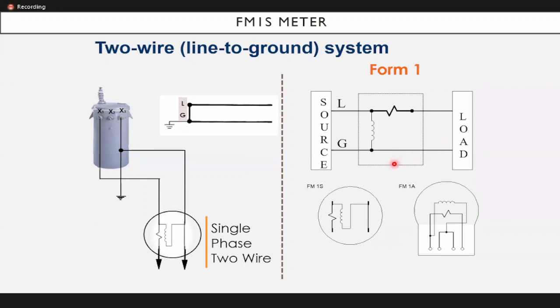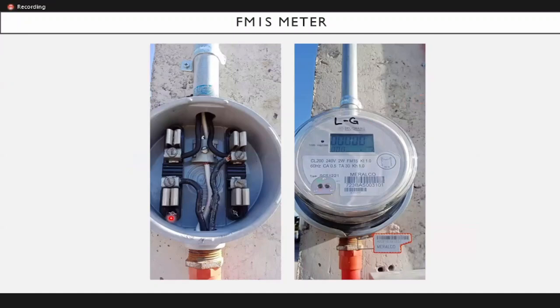And for a line-to-ground system, the meter form that we have to use is form 1. So since we're using socket type, it is form 1S. This is an example of an installation using form 1S. So this is the meter base. This is the socket type. This is the one diameter RSC, line 1 and line 2. The upper portion is the line side, and the lower portion is the load side.